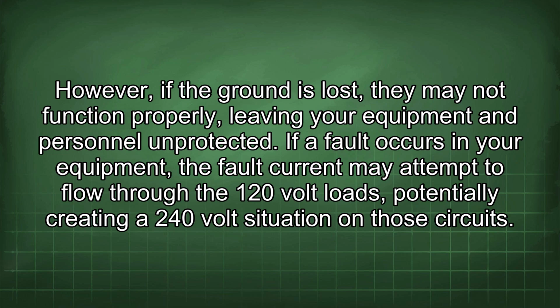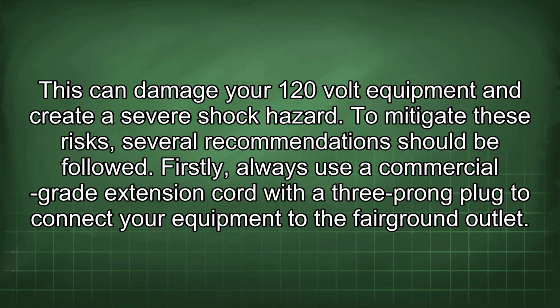If a fault occurs in your equipment, the fault current may attempt to flow through the 120-volt loads, potentially creating a 240-volt situation on those circuits. This can damage your 120-volt equipment and create a severe shock hazard. To mitigate these risks, several recommendations should be followed.